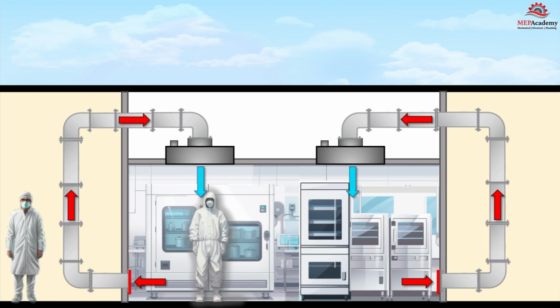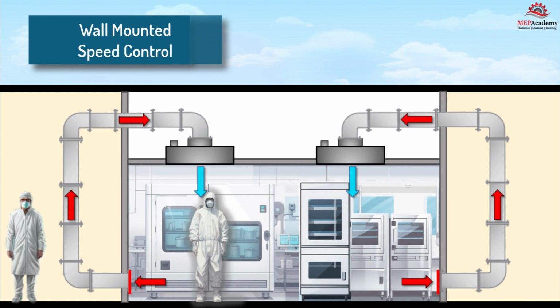In this system configuration, the fan filter units have the return air ducted directly to the unit, providing a closed loop within the clean room. This may be used where a tight plenum is not available. Fan filter units are also equipped with wall-mounted speed controls that allow for adjustable airflow rates, enabling users to control the air change rate and maintain the desired cleanliness level within the environment.